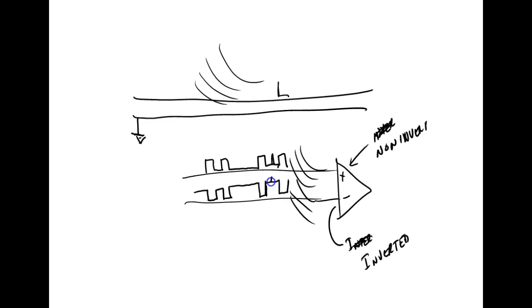We don't use a common. What a differential amplifier amplifies is signals that are different; it doesn't amplify signals that are the same. So since I'm not using a common, if these are a twisted pair of wires right there together, and electromagnetic interference comes through, it's going to put a little spike on one and a little spike on the other, but those signals are moving in the same direction.